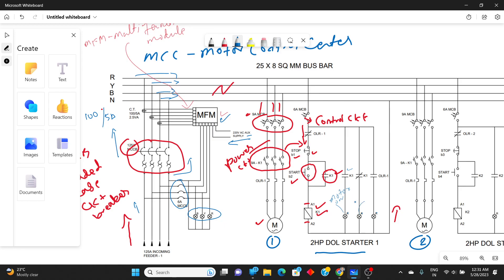One more K1 contact is taken to indicate the motor-on status via an indicating lamp. When the motor is off, this coil is not energized, so if we take a normally closed contact it provides supply to the motor-off indicating lamp. These indicating lamps show the status of whether the motor is ON or OFF. If any fault occurs in the motor — such as earth fault or short circuit — we have connected one overload relay in the power circuit.